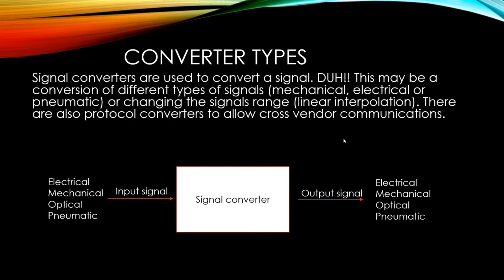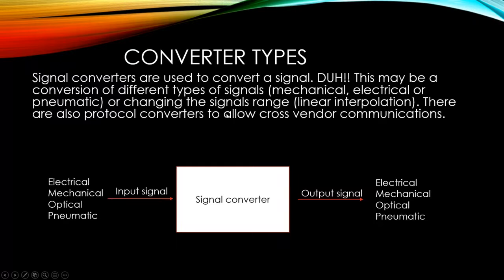What is a signal converter? Signal converters are used to convert a signal — whether it's mechanical, electrical, or pneumatic — or to change the signal's range. This is the classic input-output application done electronically, which we call linear interpolation. There are also protocol converters that allow cross-vendor communication. Different protocols like RS-232, RS-485, Modbus, HART, and Foundation Fieldbus need converters to communicate properly with each other in a control system.